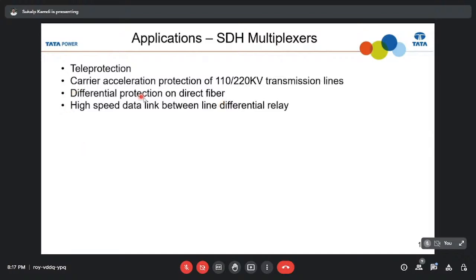So now this protection is given on direct fiber, wherein the two differential relays between the two substations are communicating on direct fiber. So this is the fastest means of communication, in 5 milliseconds, or you can say 3 milliseconds maximum. For around 120 kilometers of fiber, we have tested the delay is maximum up to 5 milliseconds, which is the fastest achieved till now for us. So this is a very high speed data link for the line differential relay.